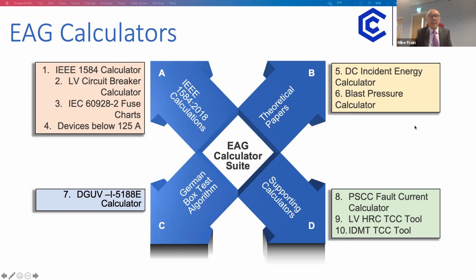Not everything is included in those calculations. I have to say clearly we are looking at thermal hazard here, and there are other hazards that aren't covered. They'll give you a good idea of whether something is more likely or not, but if you're looking at oil-filled switchgear, for instance, an arc in there that isn't cleared well can lead to catastrophic explosions and damage, and has resulted in fatalities - I know of personnel who have been killed in those positions.